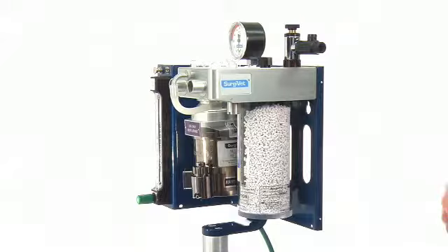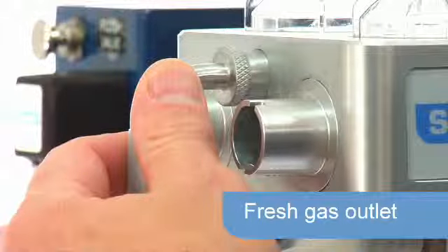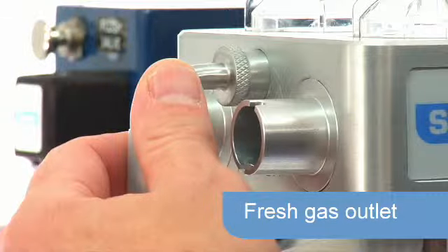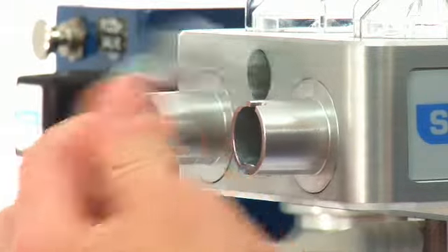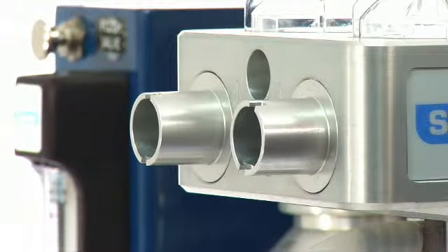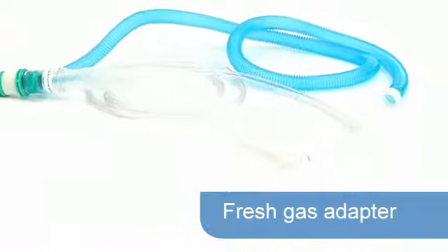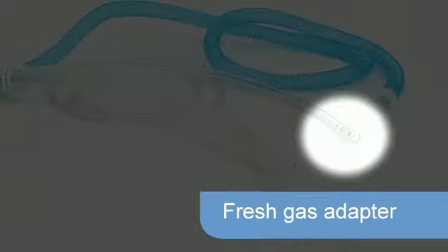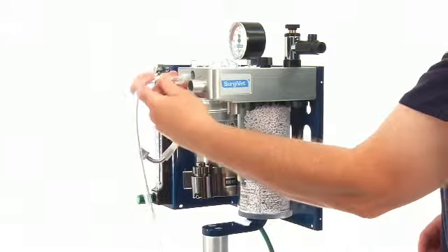To connect to the anesthesia machine, locate the fresh gas outlet on the front of the machine between the two valves. Remove the 15mm adapter from the block. Locate the fresh gas adapter of the non-rebreathing circuit and connect it to the fresh gas outlet.